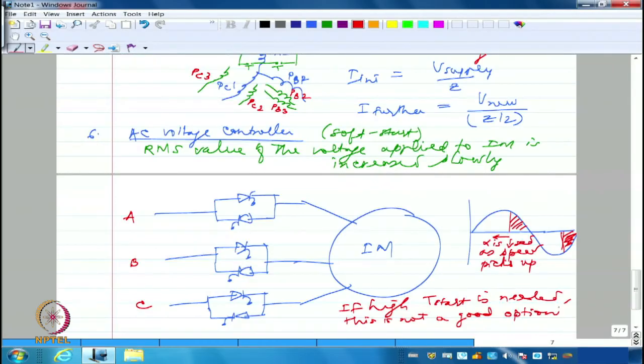This is definitely not a good option. And one more major problem is harmonics - we are definitely not looking at sinusoidal voltage or current. Everything is non-sinusoidal, so the motor can have third harmonic, fifth harmonic, seventh harmonic, and so on, which can interfere with proper working of the motor.